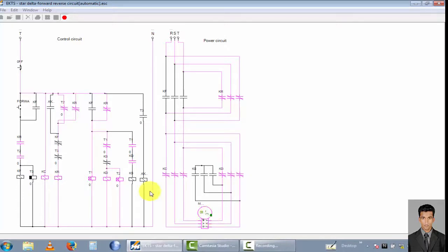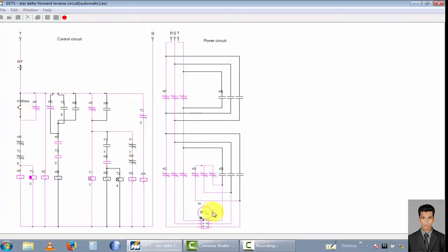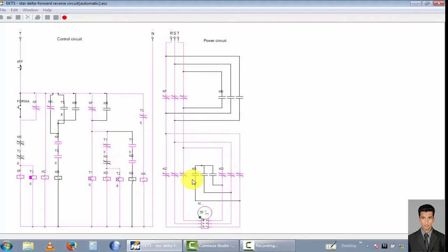Now I stop the power and go back to the forward direction. I run the motor in the forward direction again. You can see the motor rotating in the forward direction in star condition — the timer counts down from 8 to 0, then the motor changes from star to delta. This transition time is calculated as 8 seconds, after which the motor stops.